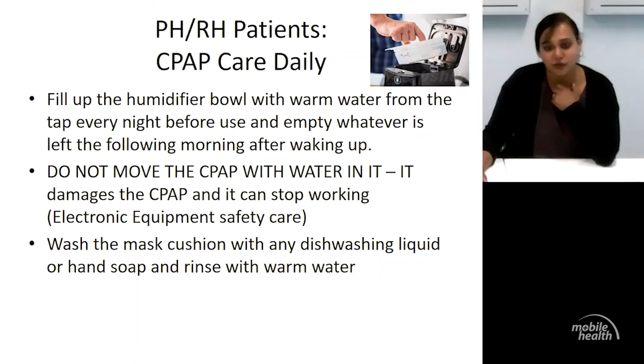And when you're fitting the mask, if your patient cannot do it themselves, then if you're doing it for them, just make sure that you're fitting the mask tighter on the bottom part. So if you have a full mask, it covers the top of your nose up to just the bottom of your chin. When you have the mask like that, just tighten the straps here so it's not easy to move up, and it's firm. If it's firm, you will not get so many problems with mask leak. But if the top one is too loose, just make sure it's touching the forehead. Don't make it extremely tight, otherwise your patient will get a headache in the morning when they wake up.